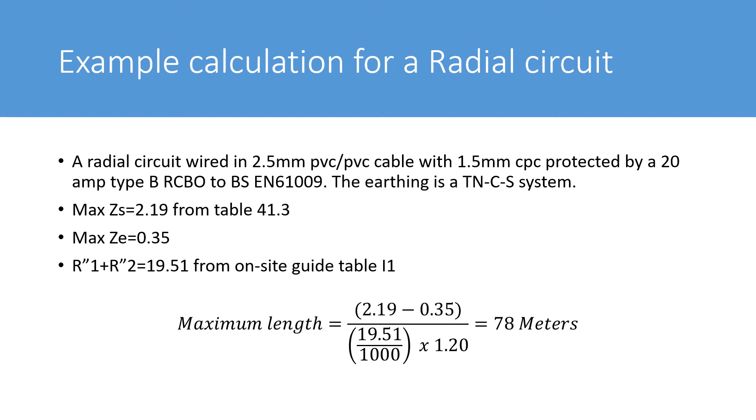So here we have an example calculation for a radial circuit. A radial circuit wired in 2.5 mm PVC-PVC cable with a 1.5 mm CPC protected by a 20 amp Type B RCBO to BSEN61009. The earthing system is a TNCS or PME system.